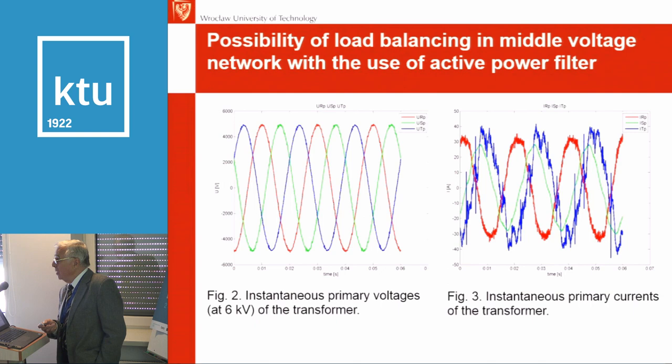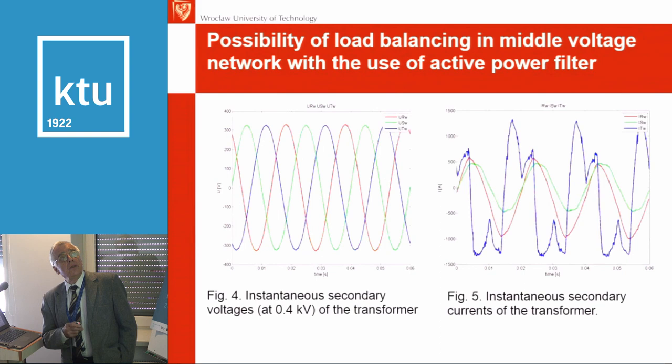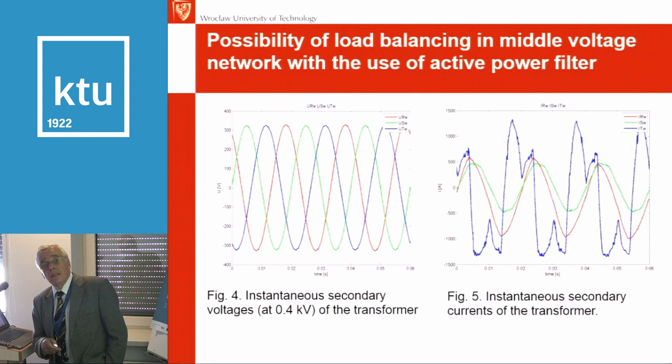On the secondary side, as you see, the voltage also looks symmetrical without any problems. However, for the current there is a tremendous difference, up to about 200% between particular phases, and the angle shift is also very different. Therefore, in the secondary we really have problems.